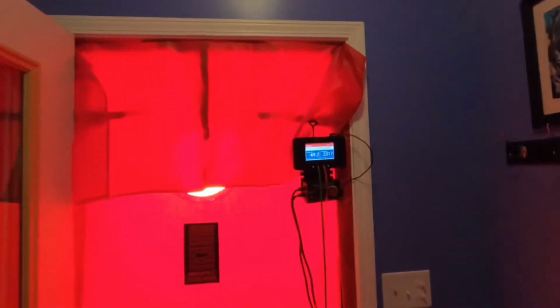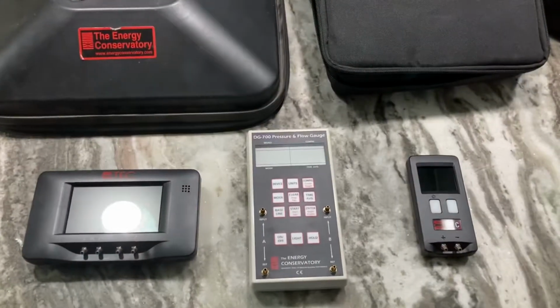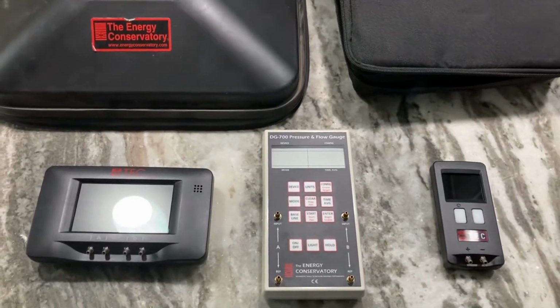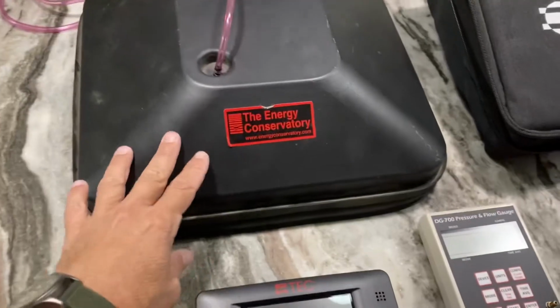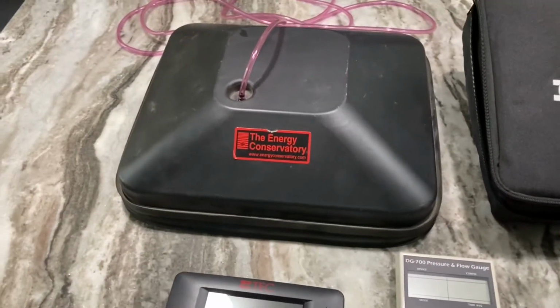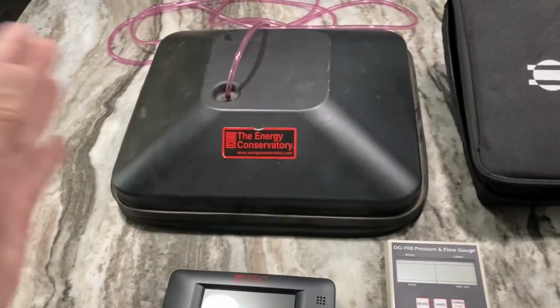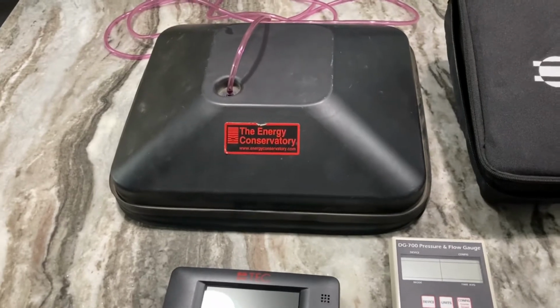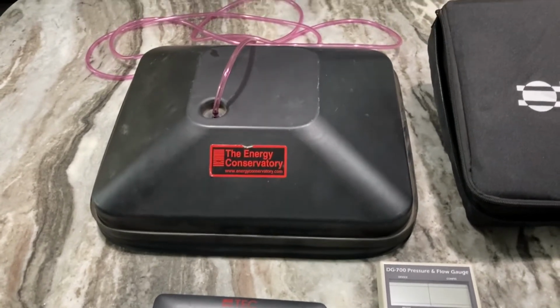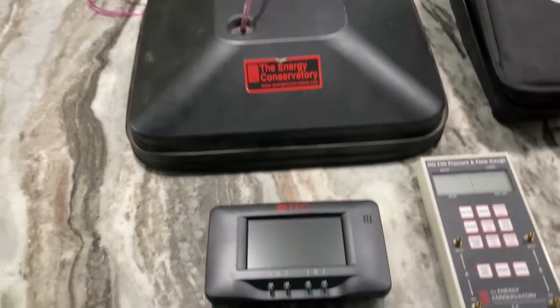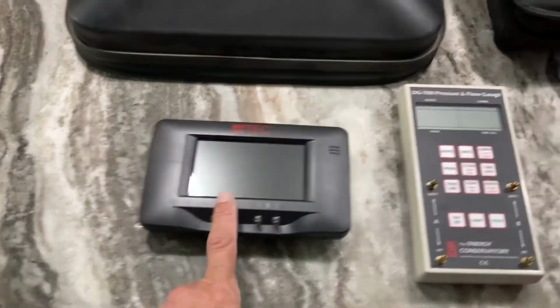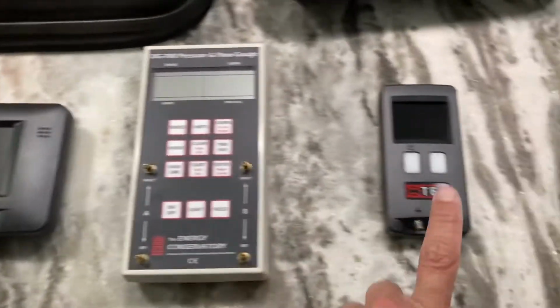Pressure pan readings are taken anytime we have ductwork running through unconditioned spaces like attics, knee wall areas, possibly crawl spaces. It tells us how leaky that ductwork is into those spaces and if we need to call for duct sealing. We'll do this with the DG1000, the DG700, and the DG8 single channel manometer.